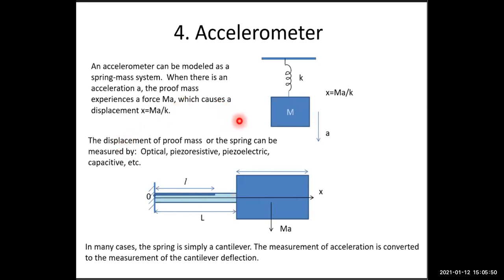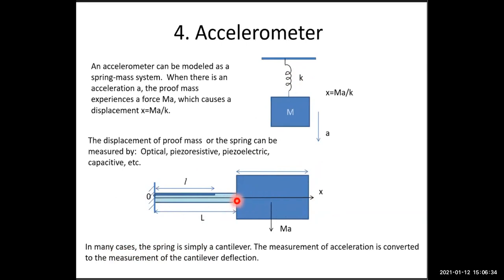So the measurement of acceleration is converted to the measurement of displacement of the mass on the spring. The displacement of the mass and spring can be measured using optical, piezoelectric, capacitive, and other sensing methods. In many cases, the spring is a cantilever beam and the mass is attached to the end of the cantilever, so the measurement of acceleration is converted to the measurement of cantilever deflection.